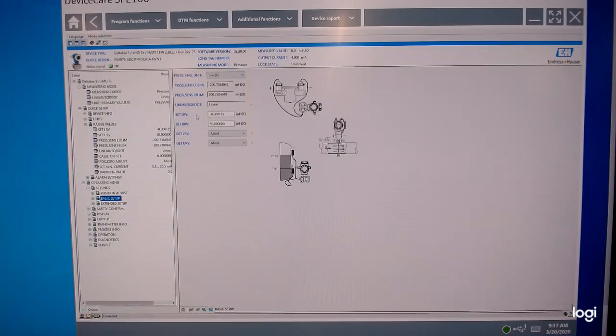In basic setup, you can see over here that we have a set LRV and a set URV, and then we have a get LRV and a get URV. So the set ones are our dry calibration. Now what that means is that we're actually using the factory calibration of that sensor, and all we're doing is just picking 2 points. This is very similar to doing our upper and lower range value, just setting them. It's the same thing here really. The only difference with this is that we're actually telling this thing that these are the 2 points I want you to linearize between, but we're going to use the factory characterization of the sensor for this, okay? We're going to use the factory characterization.